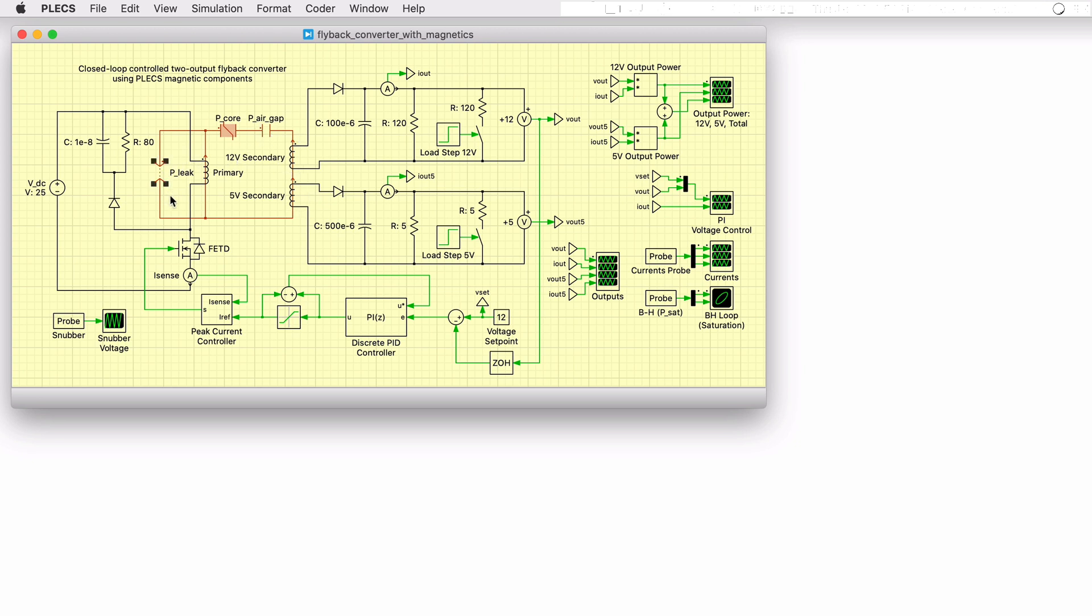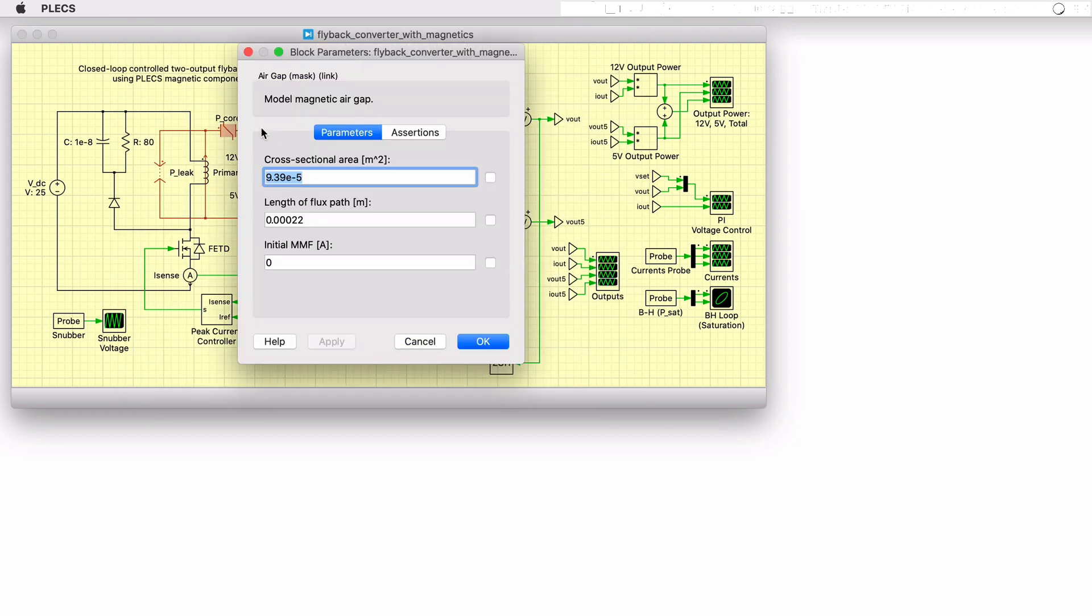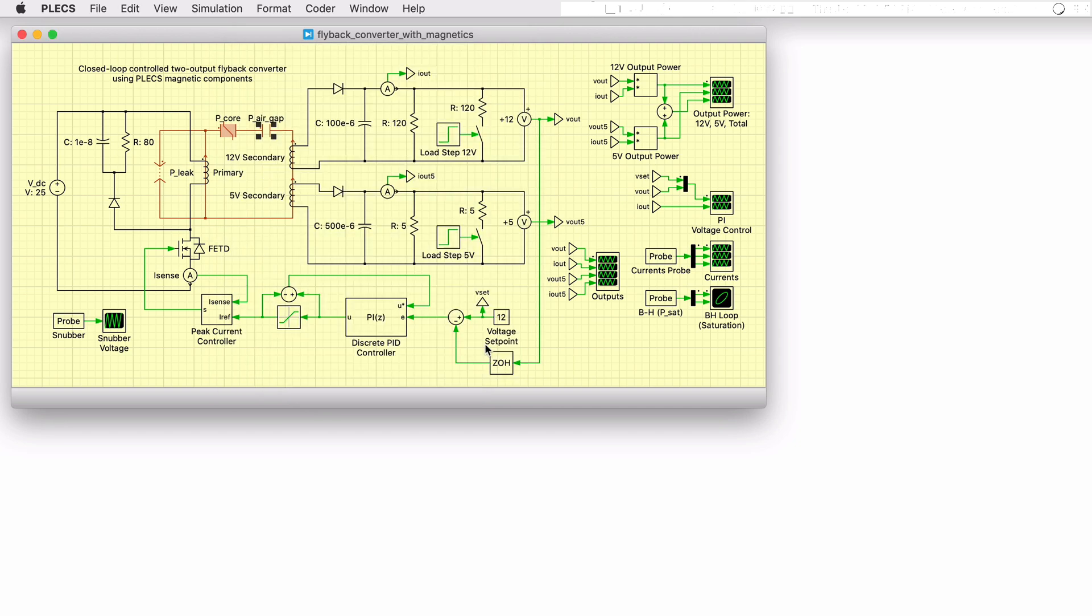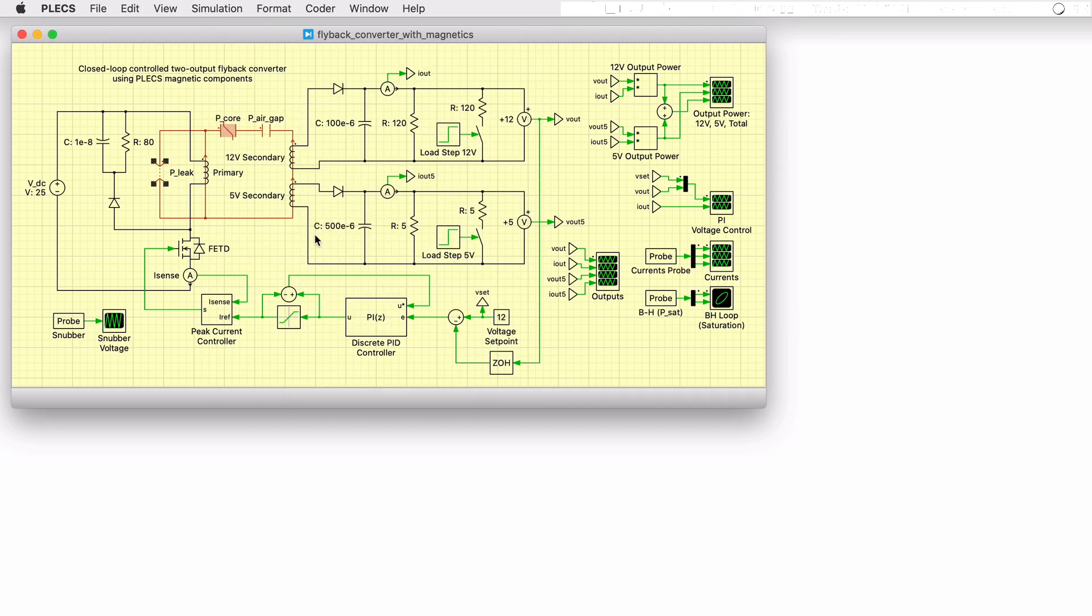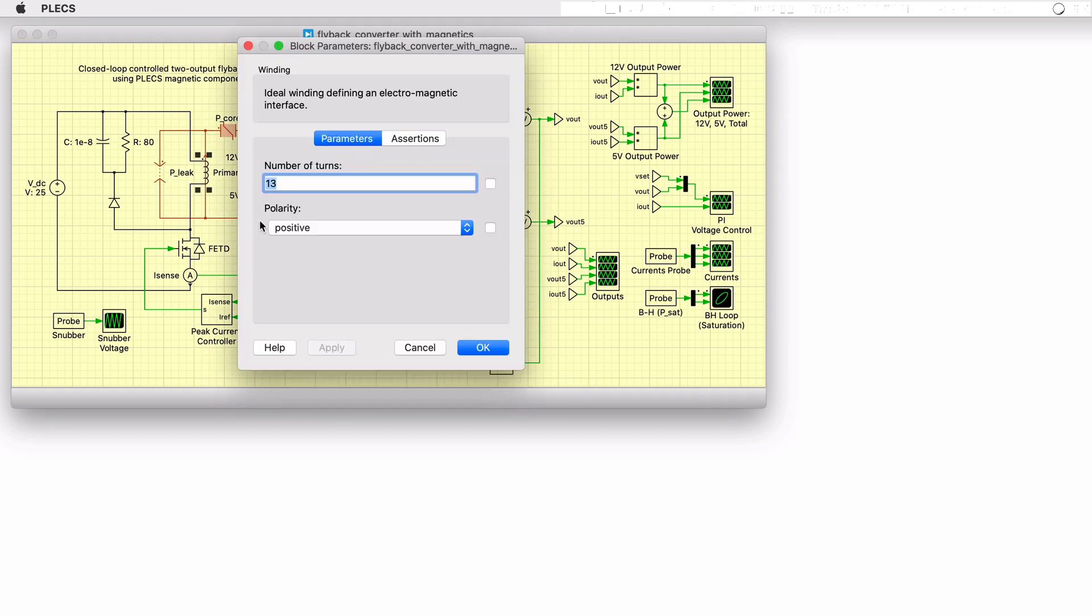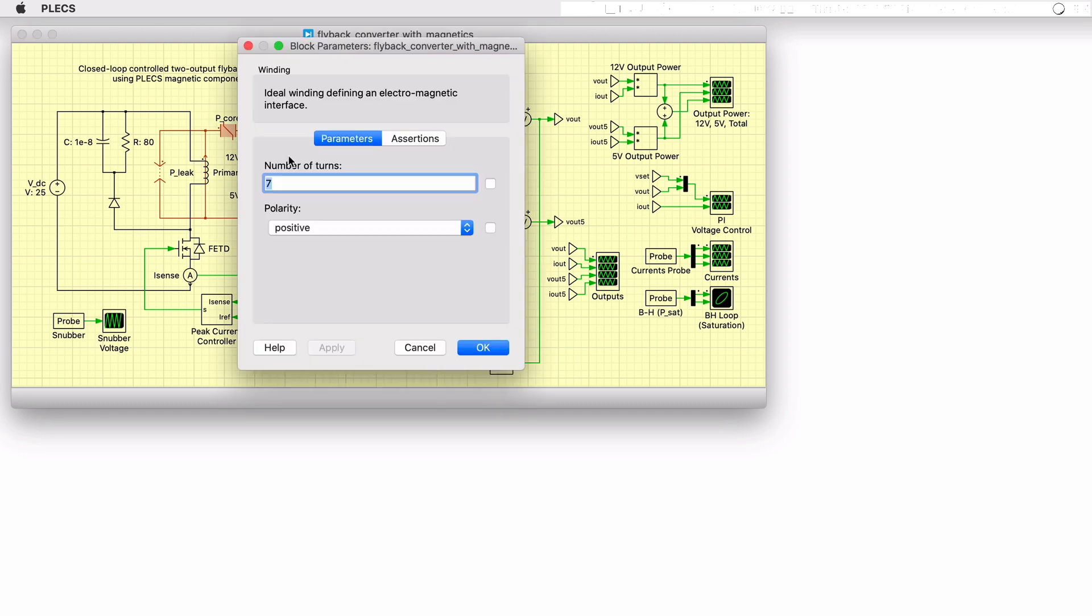Using the information for the transformer core's magnetic path length and core cross-sectional area provided in the material datasheet as well as the output design specifications, one can calculate values for saturation characteristics, the length of the air gap, leakage path permeances, and the number of turns on the primary and secondary side windings.